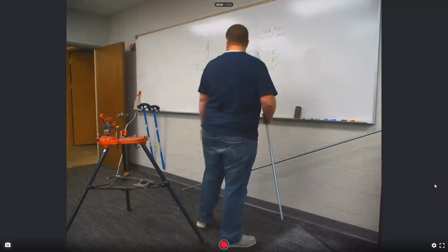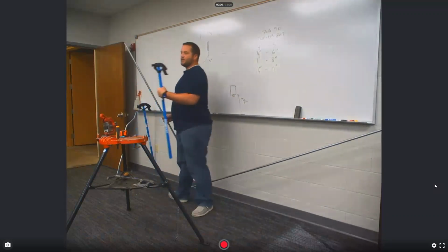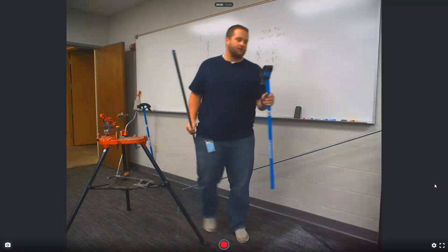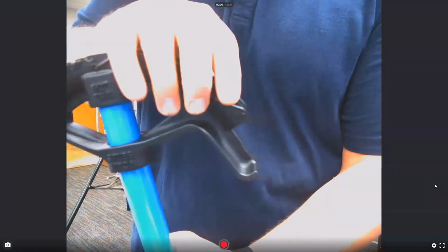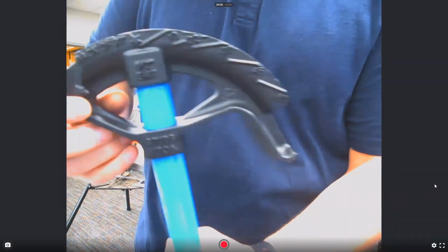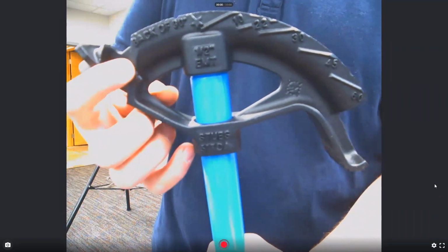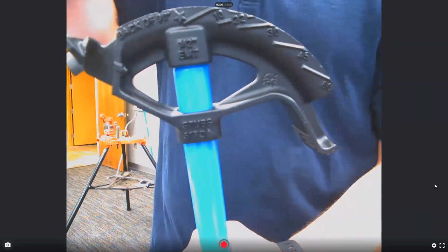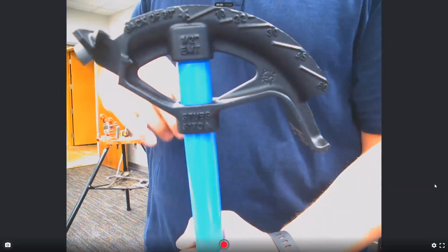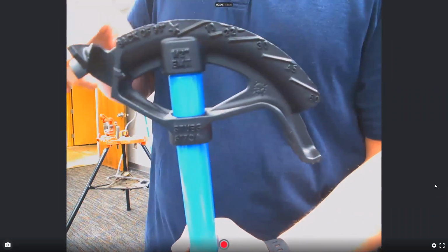Okay, 4 3/8. Look in your Uglies book and tell me what mark on the bender I'm supposed to put that on. You've got all sorts of marks on this thing. The arrow, which is right here. Most of your bends to start with, you're going to use the arrow. The arrow indicates the start of the bend or the start of the radius. But you will use all these marks in this class in your labs.